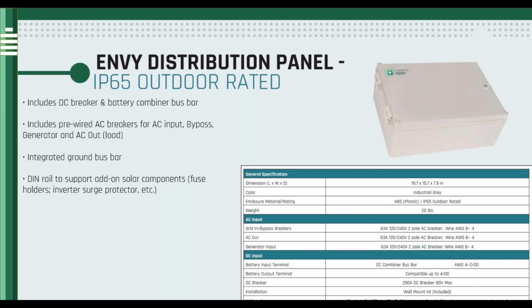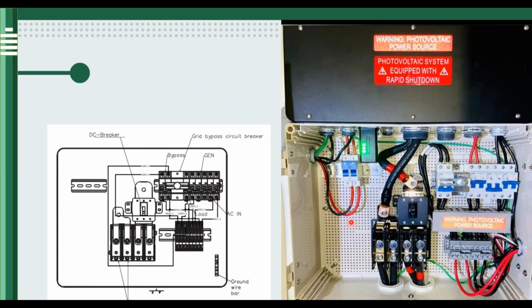Awesome. Okay, so for the Envy distribution panel, this is a box that we designed for the 8K and 10K. It comes with all of the AC and DC breakers that you would need to make this connection, right? It comes with a 250 amp battery breaker, and three AC breakers of 63 amps, one for generator, one for the AC input, and one for the AC output, as well as a bypass breaker, as displayed here. This is the bypass breaker.